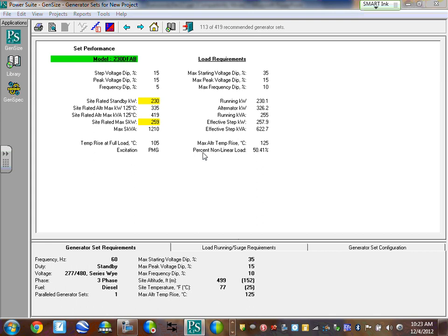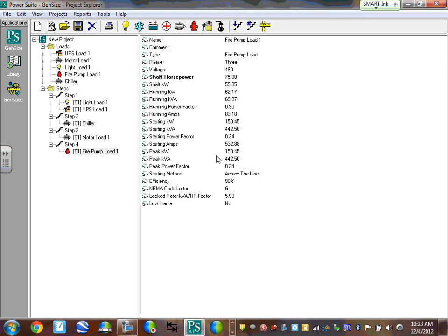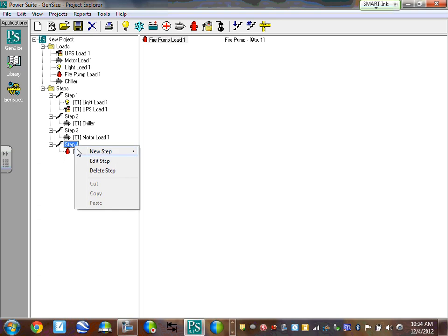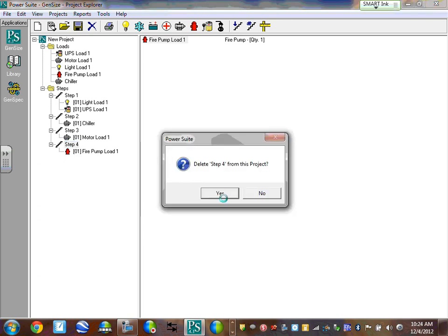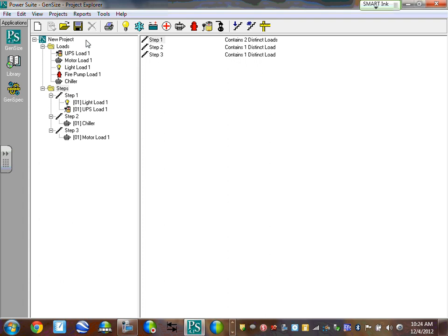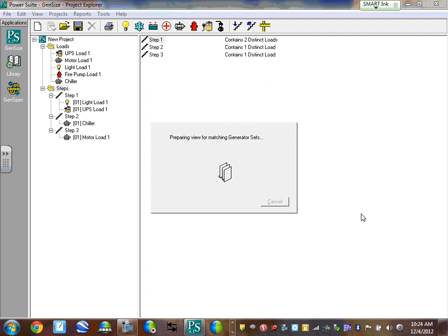This particular program also tells you the percent of the nonlinear load, which is a very good thing to know. Now, the owner can't afford that. He's saying, well, I'm not so sure that we have to put the fire pump in. What do you think? So they check and they say, okay, we'll take the fire pump out. So now we'll go back and we'll completely remove this, delete that step, so we don't have a fire pump in there. Now we'll go back, resize it.